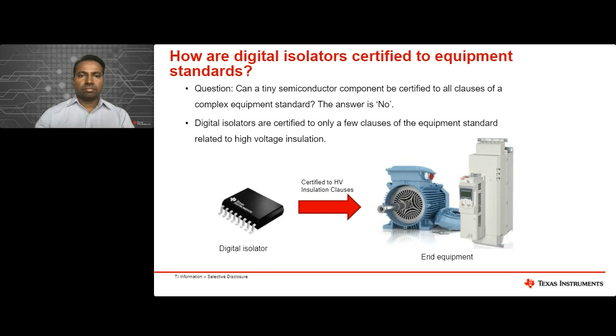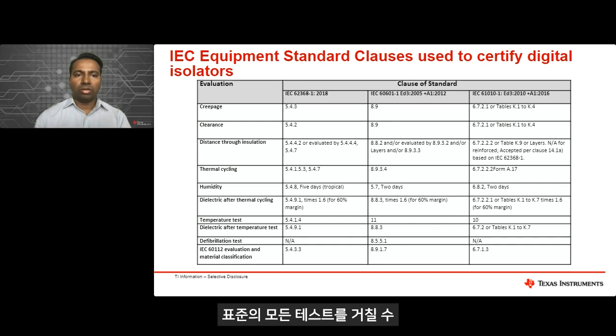Here's a list of such clauses that apply to isolators from the equipment standards. Creepage, clearance, distance through insulation, thermal cycling, humidity, dielectric test after thermal cycling, after temperature test, defibrillation test, and material classification. All these are the tests from these end equipment standards that apply to isolators, and the isolators are only tested for these specific tests, and hence they cannot be tested for all the tests in the standard.